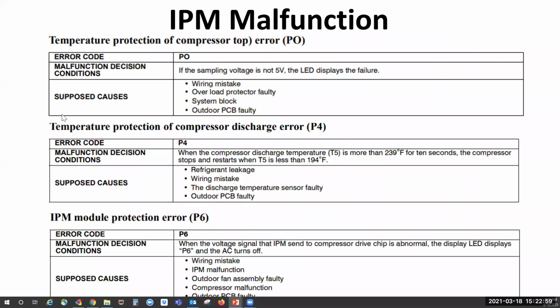We're going to get into the IPM malfunction, temperature protection, compressor, the P0, the discharge error, the P4, and the IPM module protection of a P6. Now, it's a good idea if you walk in and find out that you have a code that starts with a P, it's best just to go on outside and see what's going on outdoors.